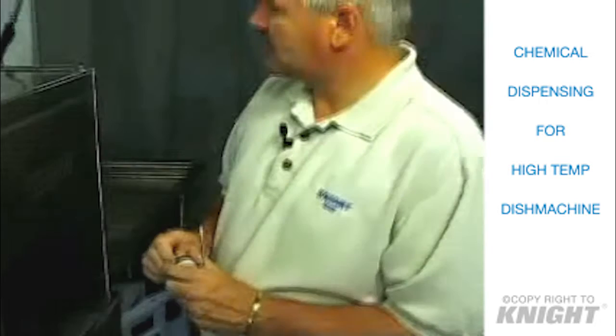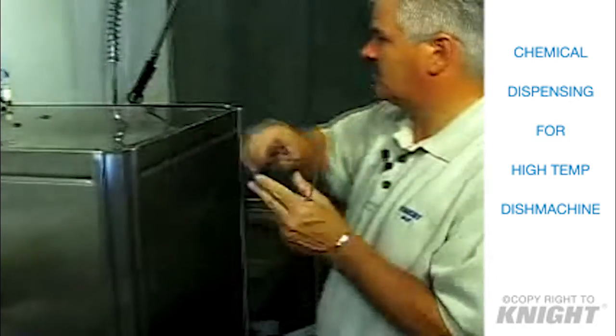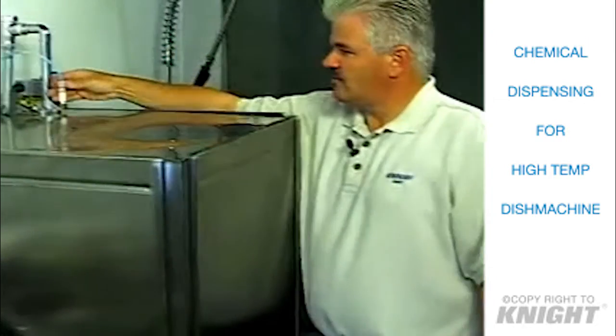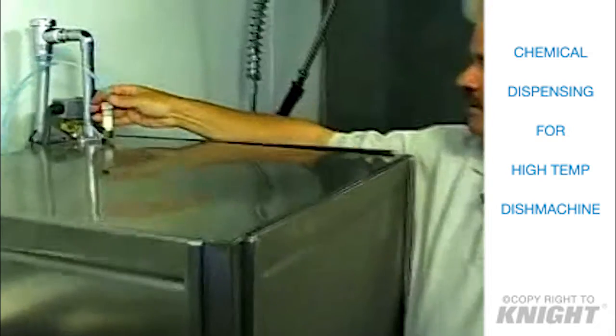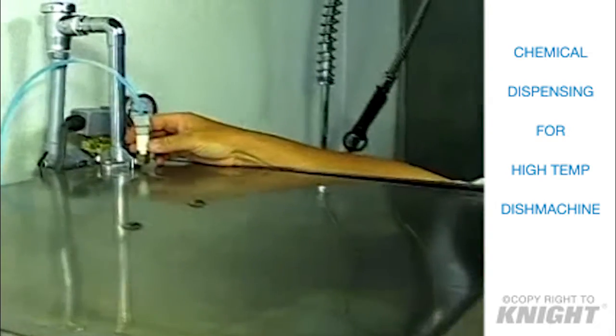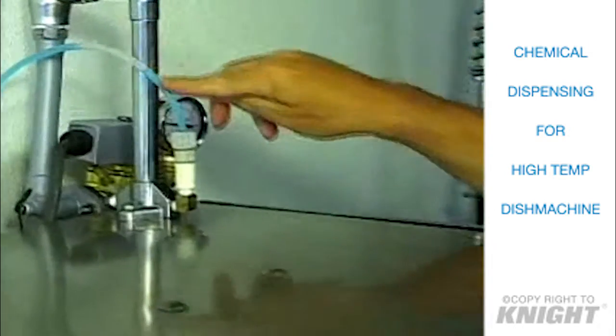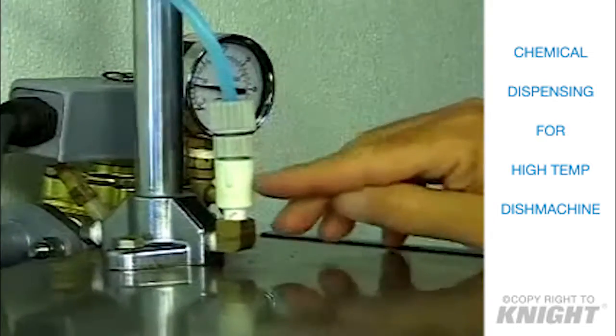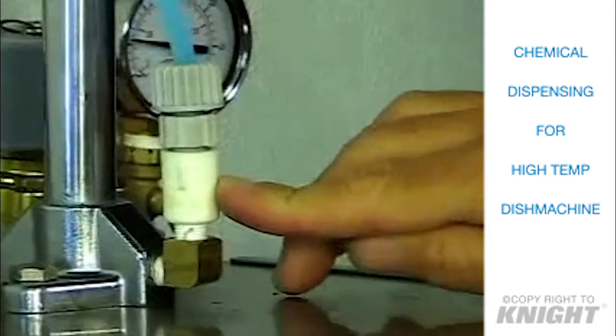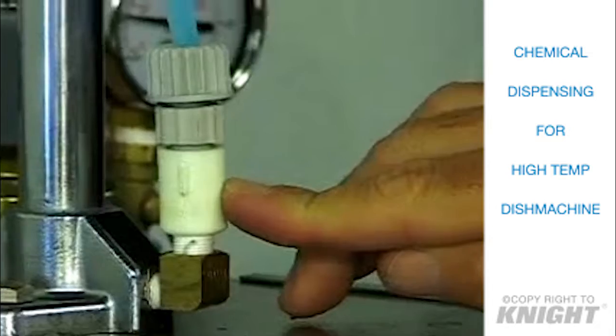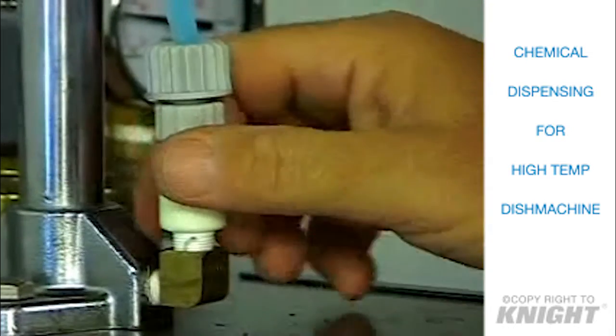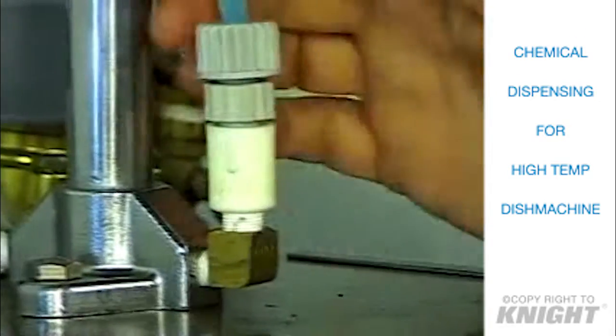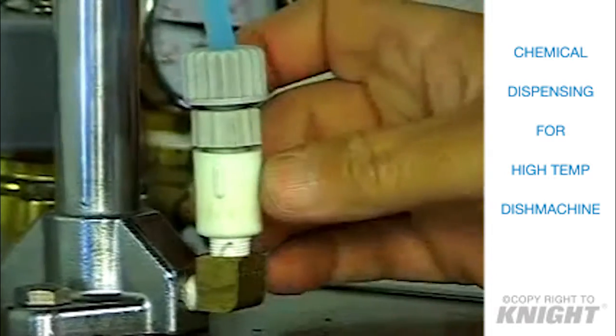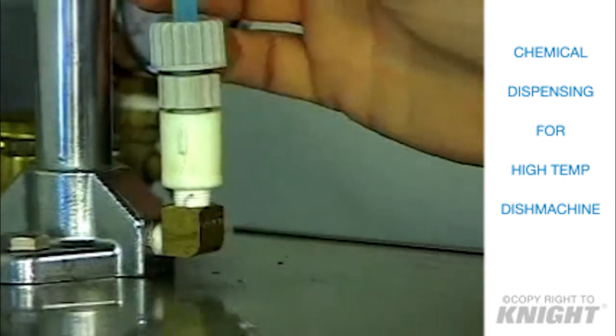Another thing to be looked at is our rinse injection fitting. The rinse injection fitting is very important because inside of it there's a check valve. So when your chemical runs through this line and comes down in here, this duckbill or poppet, depending on which check valve is inside of here, eventually may start to deteriorate from the pressure that's being put on it from the water or from the product that's going through it.